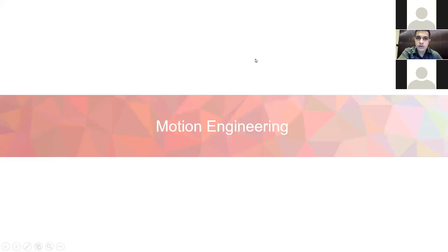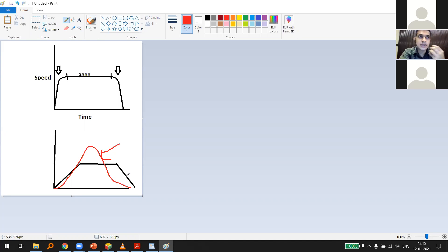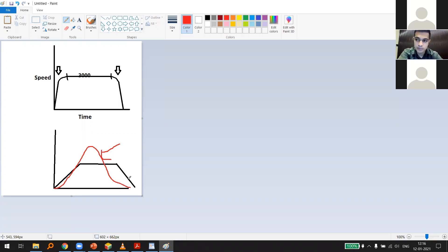Motion engineers use electronic cam (eCam) design or gearing to change the speed profile. Beyond the trapezoidal curve, you can use a sine curve for an even better servo response. Most robot movements use a sinusoidal speed profile rather than trapezoidal — there is no abrupt change in speed anywhere in a sine curve, so you see no jerk at all.